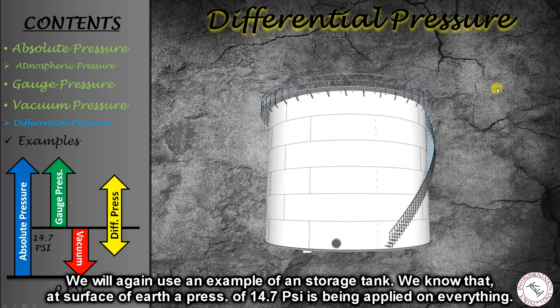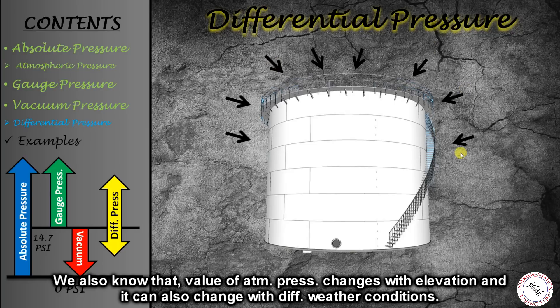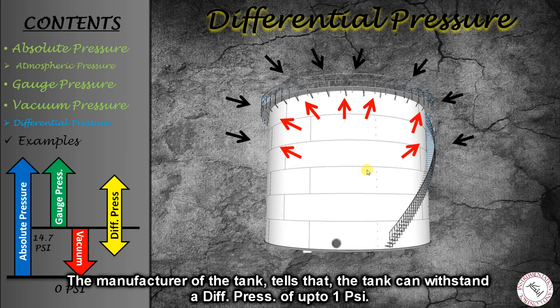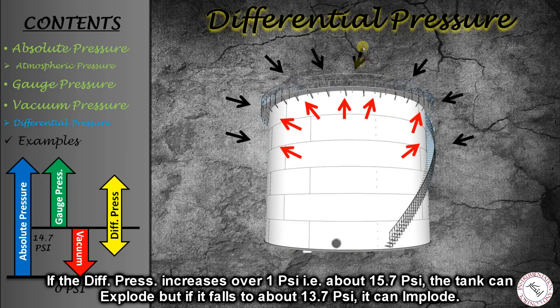To understand differential pressure, take the example of a storage tank. We know that absolute pressure of 14.7 psi — atmospheric pressure — is continuously applied to every object. The manufacturer of a tank tells us that the tank's structural strength is such that if the differential pressure — meaning the difference between outside atmospheric pressure and the inside vapor pressure — exceeds a certain limit, say 1 psi, the tank can explode. Conversely, if the internal vapor pressure is 1 psi below the atmospheric pressure, reaching 13.7 psi, the structure can implode.